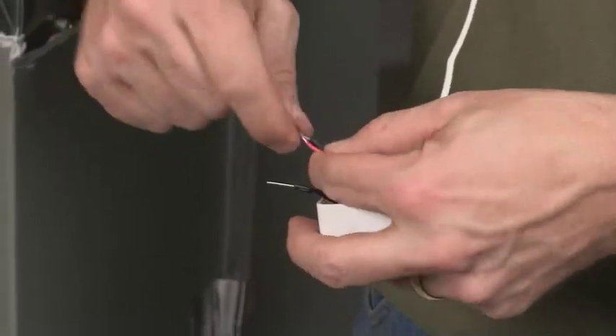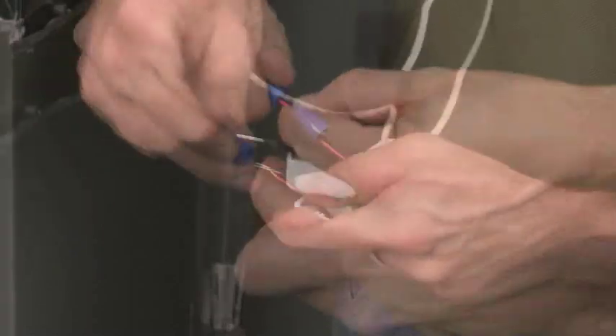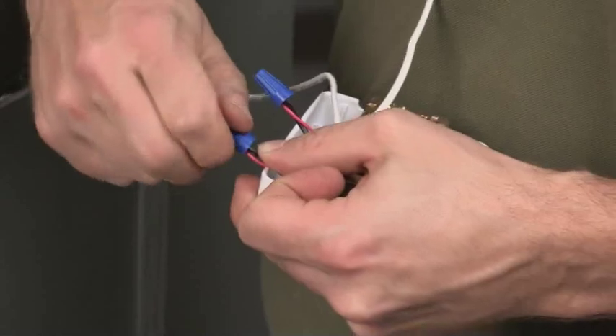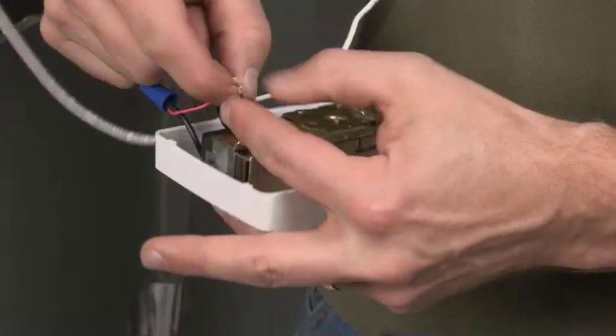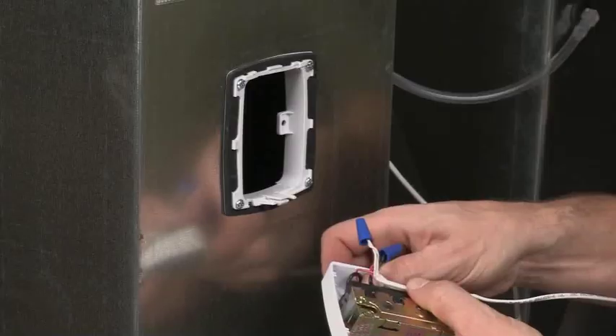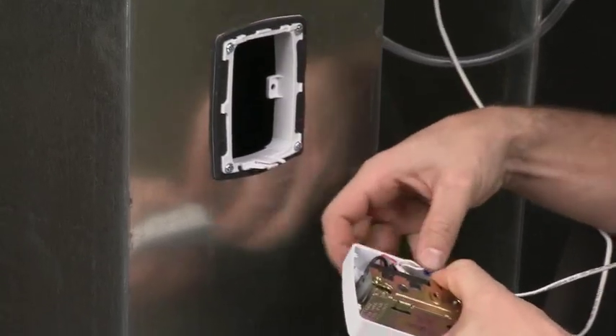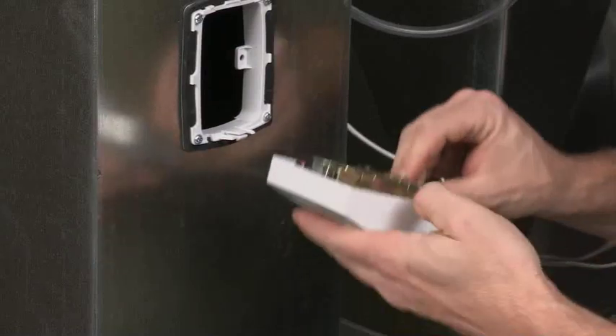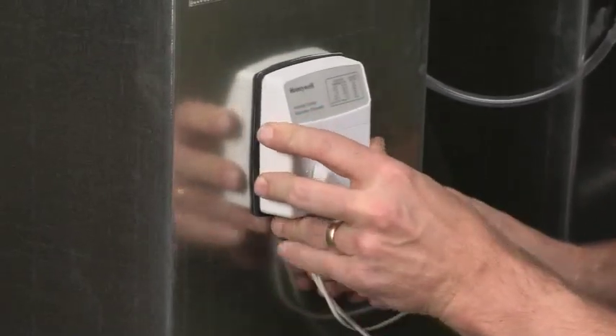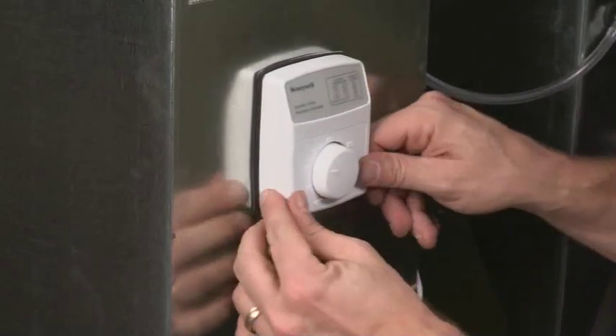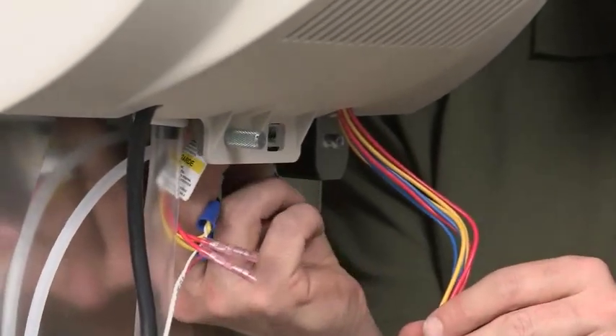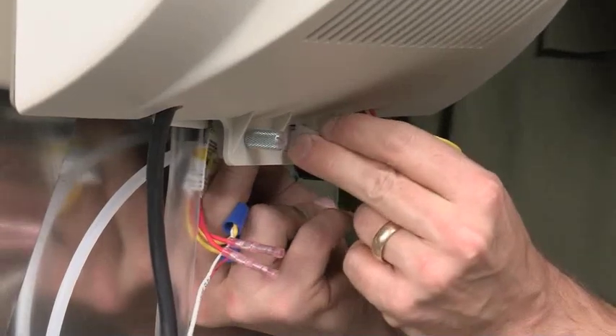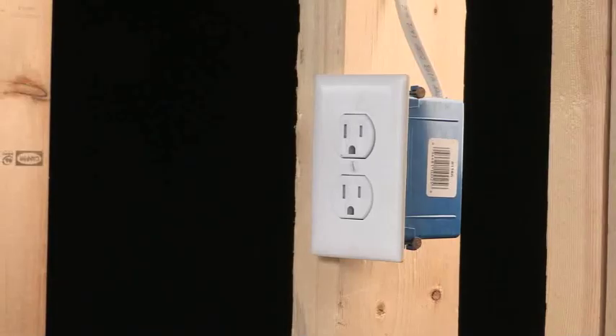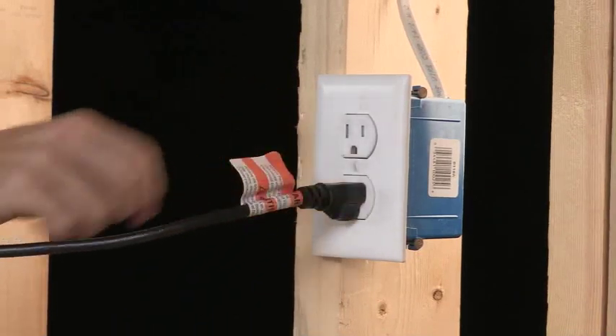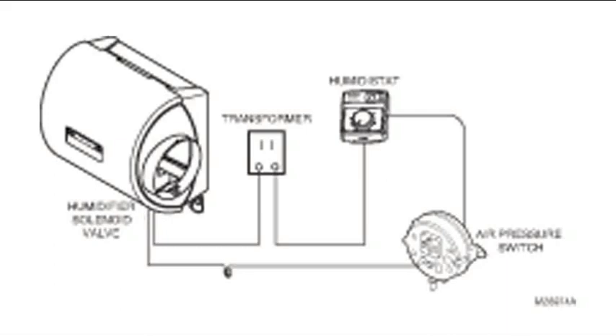At the humidistat, connect the red conductors coming from the humidifier and the pressure switch to the 2 black humidistat terminals. Use a wire nut to connect together the 2 white conductors. Tuck in the wires and snap the humidistat onto the base. Connect the wiring harness from the humidifier cover to the humidifier base. Plug the power cord into a 120-volt outlet. Your written instructions include additional information and drawings, which can further help explain this wiring procedure.